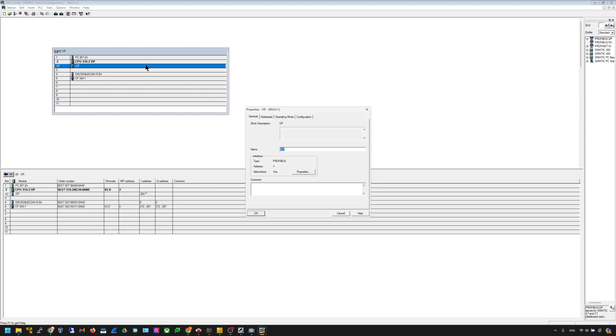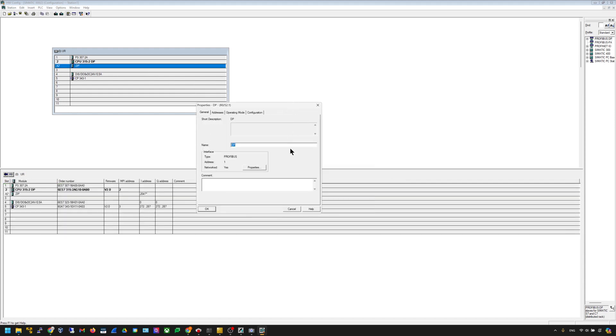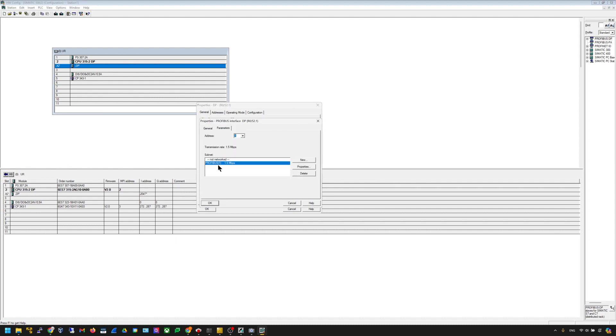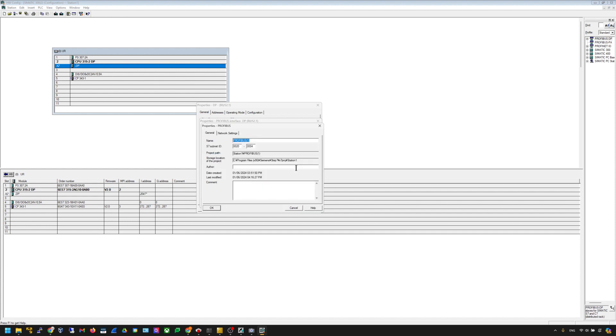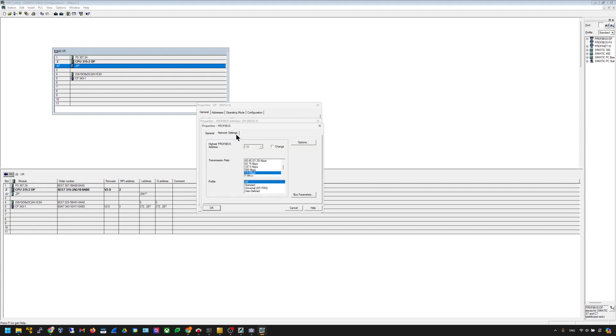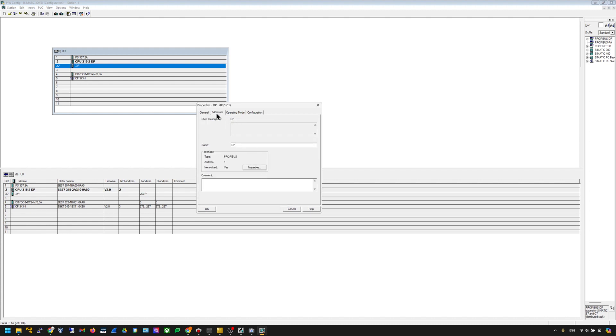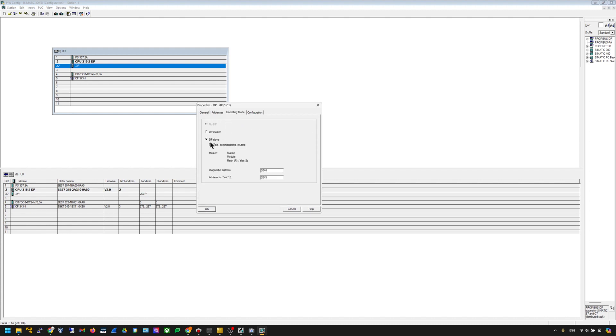Click the DP port and open its properties. First, choose Profibus and set the Profibus address — make sure this address is not duplicated on your Profibus network. Then click Properties again and go to Network Settings. Make sure you select DP mode and that the transmission rate matches all nodes and your master. Verify all settings are correct.